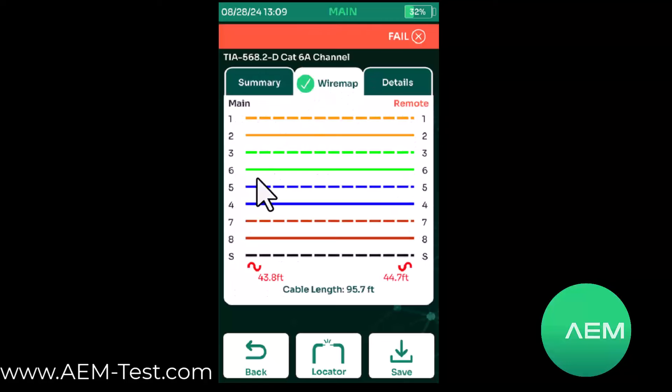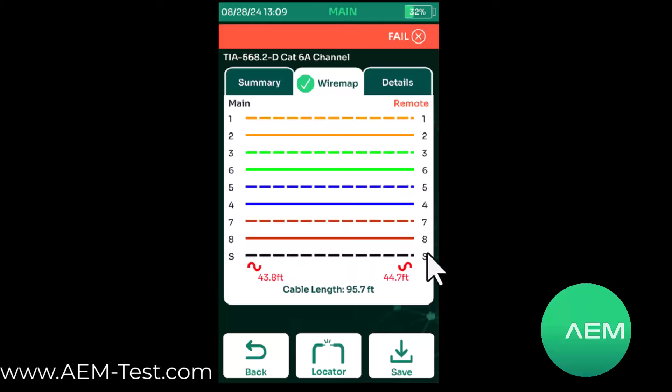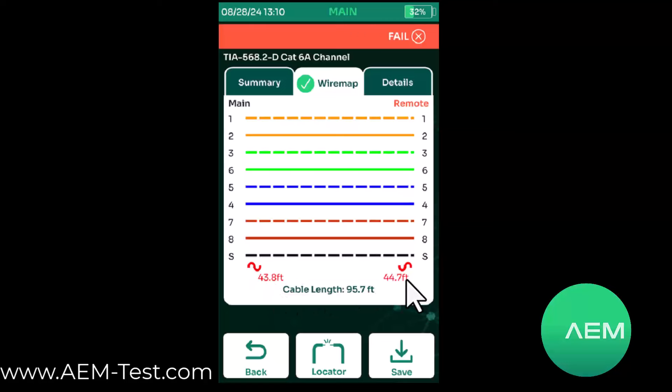Now if we look at wire map, wire map passed. On a simple wire map tester, you'll see that shield has continuity, and you might think it's a pass. In this case, we've got an indication that roughly 43 feet from the main and about 44 feet from the remote, this is the test pro, we have an issue.